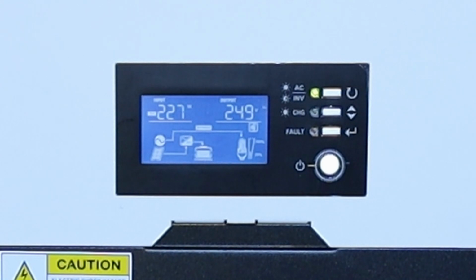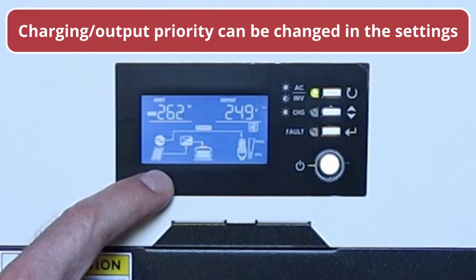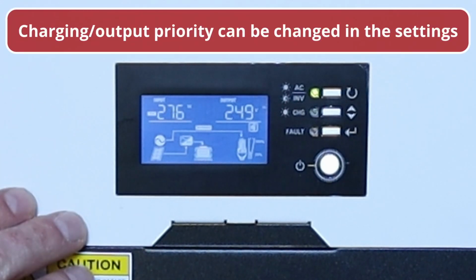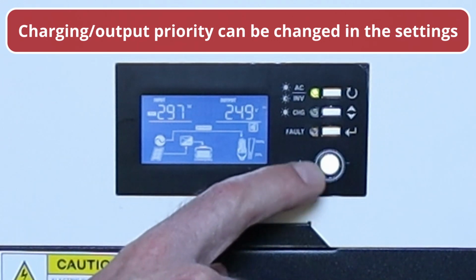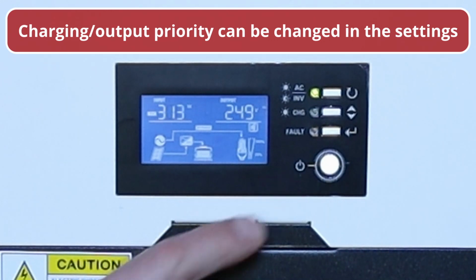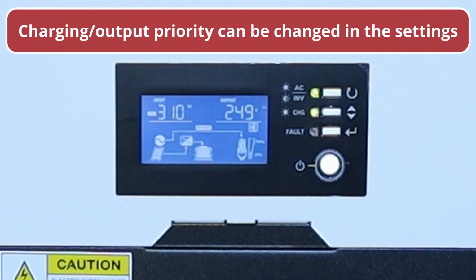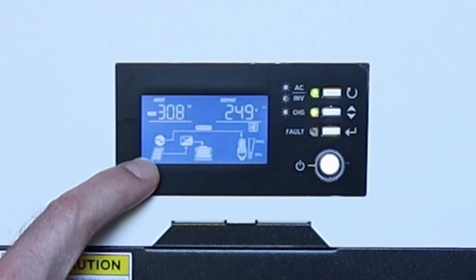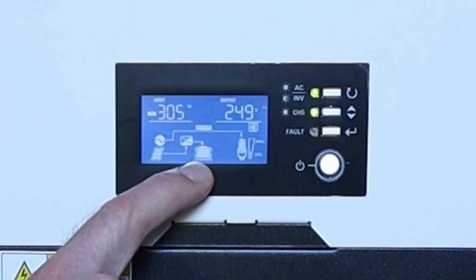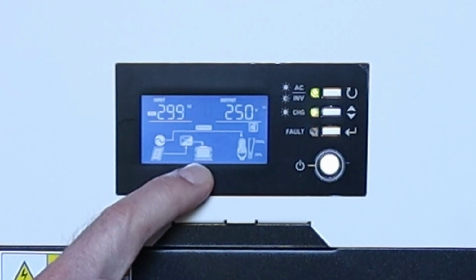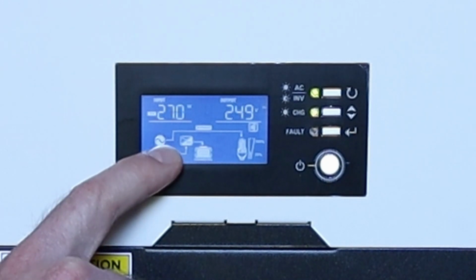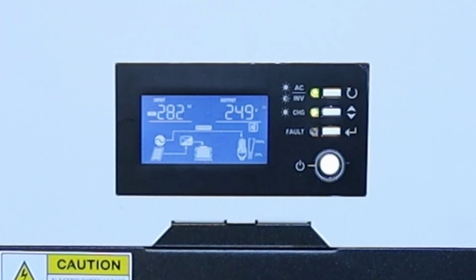You can actually see there where it's changed its charging profile, and that can be set up within the unit itself, using the software, or using this front panel here. I've got the priority charging for the battery coming from solar, and as you can see the solar panel is going in and charging the battery directly, but the mains has now bypassed that and is going straight to the load.